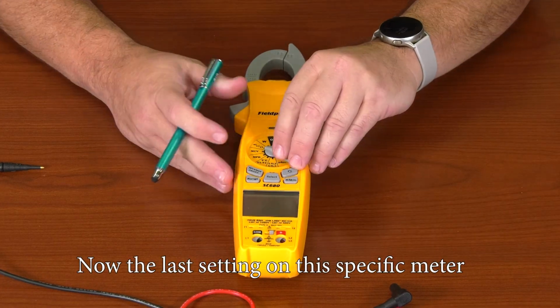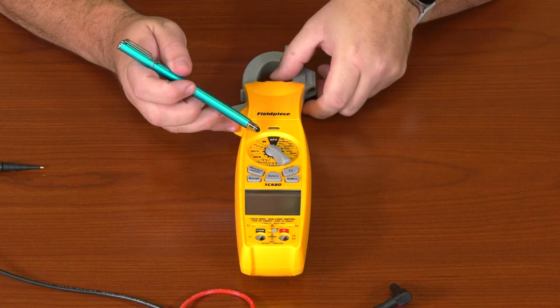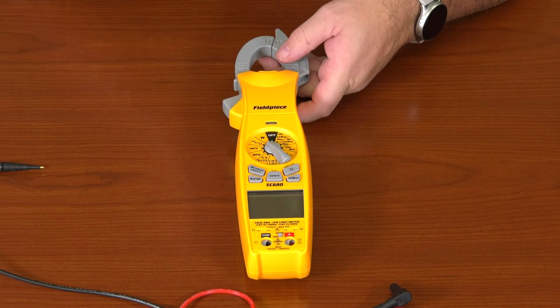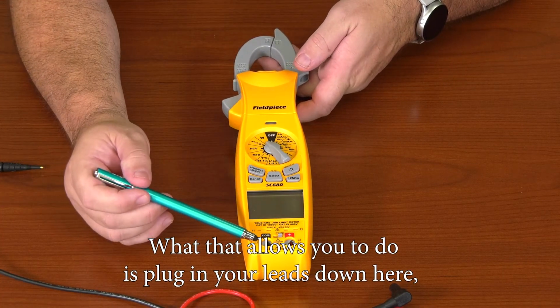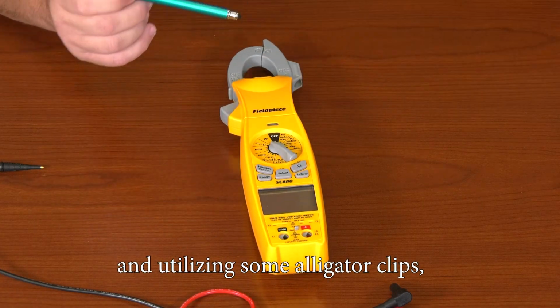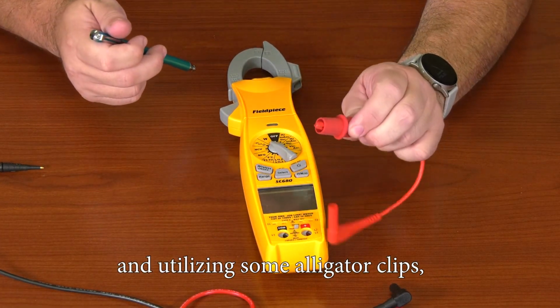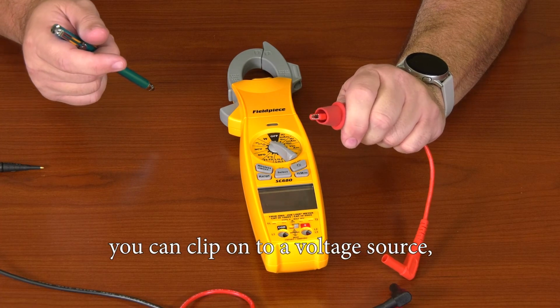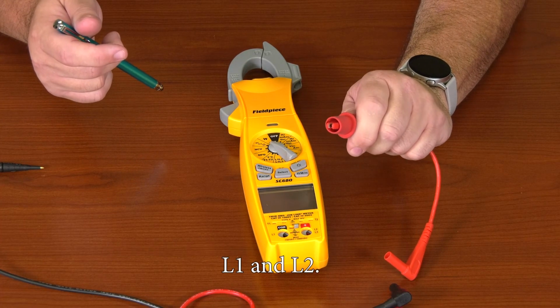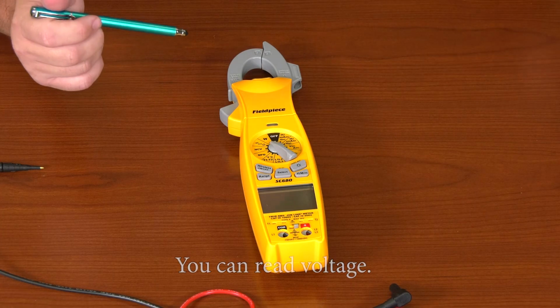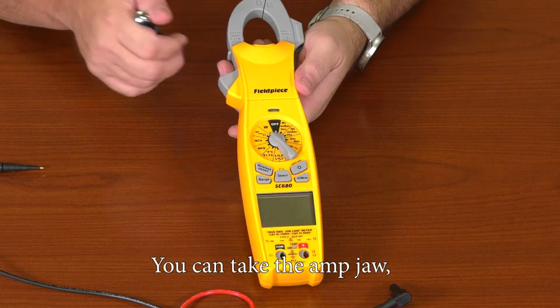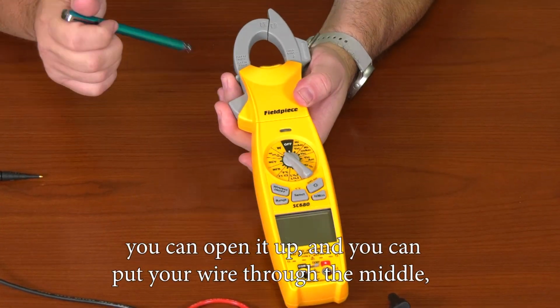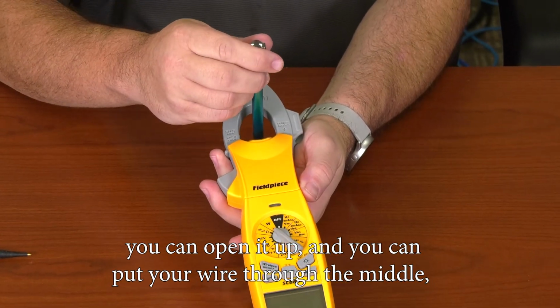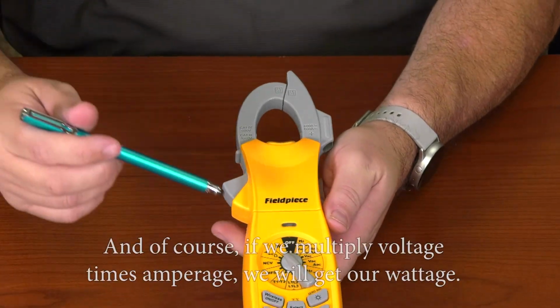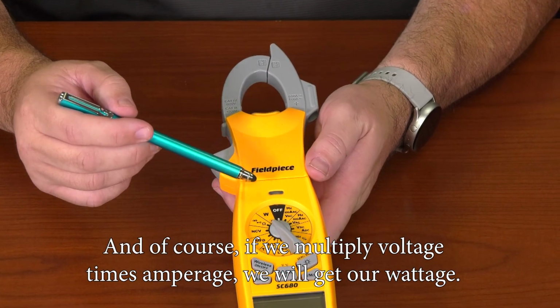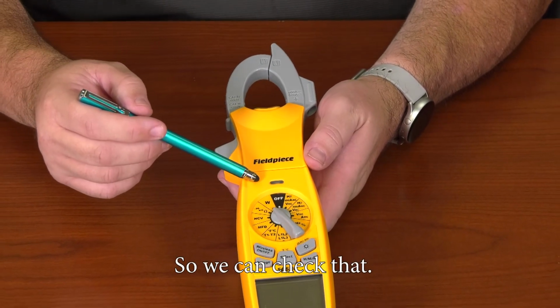Now the last setting on this specific meter is W for wattage. What that allows you to do is plug in your leads down here, and utilizing some alligator clips, you can clip onto a voltage source, L1 and L2. You can read voltage. You can take the amp jaw, you can open it up, and you can put your wire through the middle, and that will measure amperage. And of course, if we multiply voltage times amperage, we will get our wattage, so we can check that.